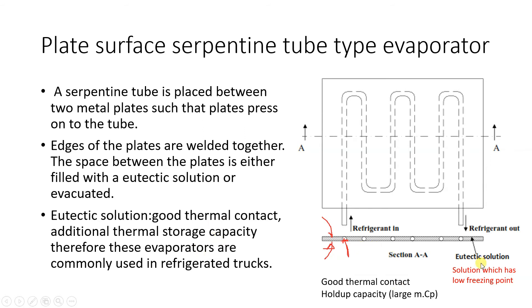The eutectic solution has a low freezing point. In the refrigerated truck application, a ground-based refrigeration system chills the evaporator and freezes the eutectic solution. When the truck travels, the ground refrigeration system is disconnected. The chilled eutectic solution maintains the cold temperature inside the truck over a large distance without requiring a refrigeration system on board.